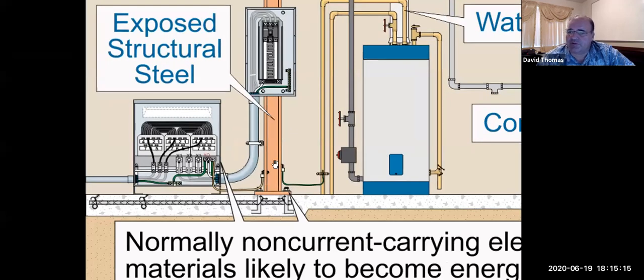So what we did is we took the structural steel and we used it as a point to bring everything together. So we bonded our electrical system to the building steel, and if the building steel is going to earth properly, because sometimes building steels will actually float. So what they do is they'll actually have it float, like for earthquakes and seismic activity.